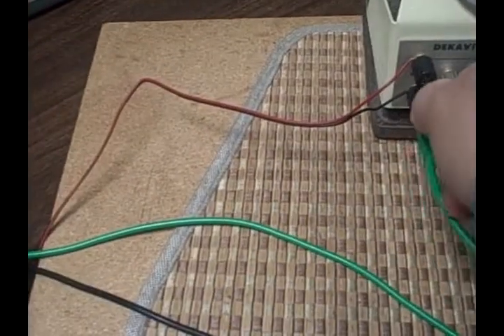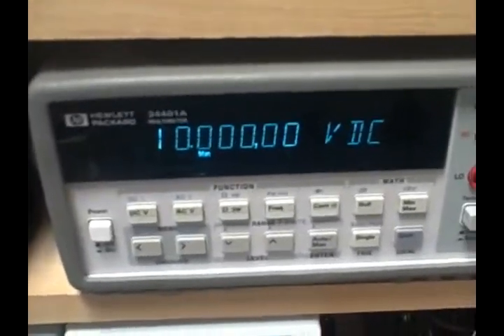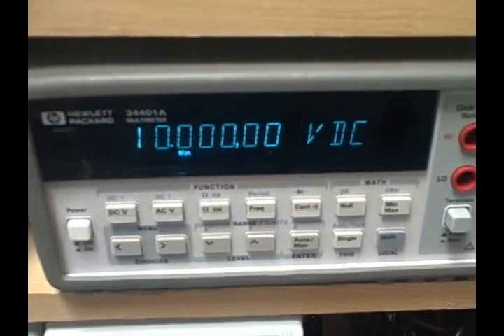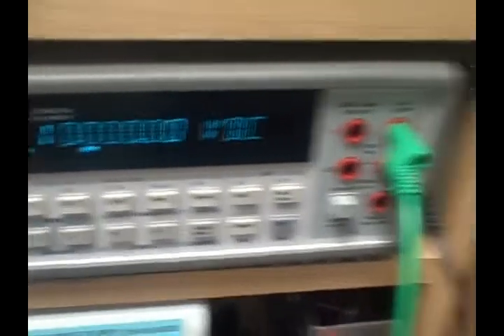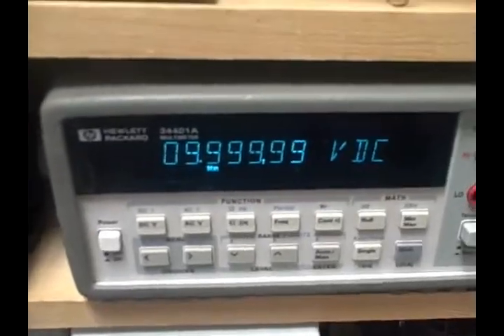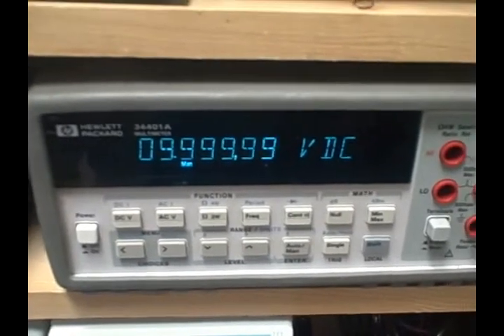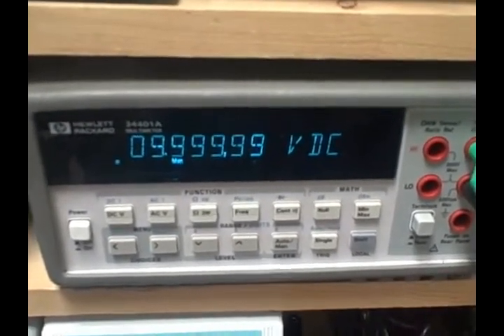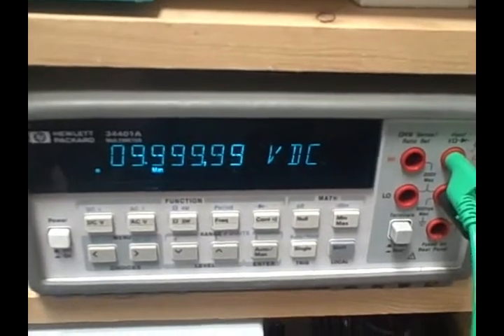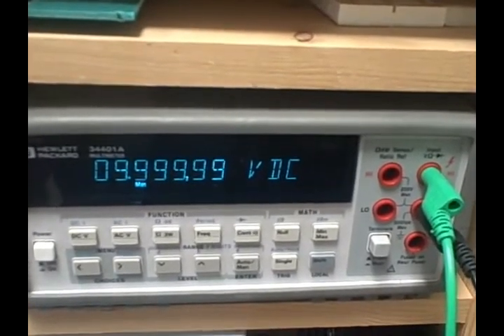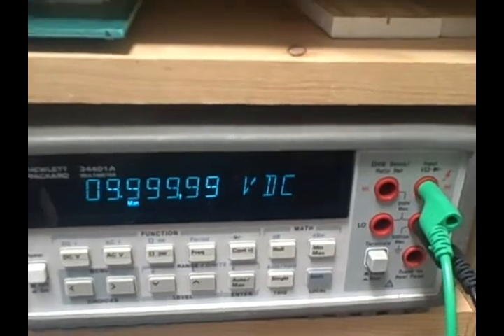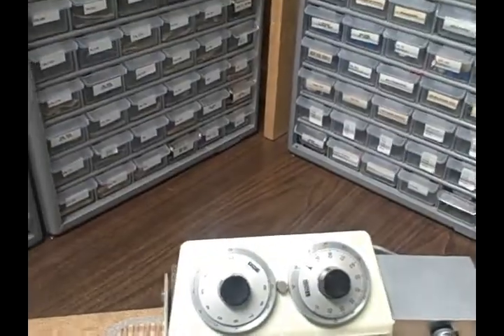And if I take a look at the input to the divider I see that I'm getting fed 10, with five decimal places of zeros in volts. And on the output I am getting all nines. So I'm within 10 microvolts of achieving a perfect 10 which would be the input voltage at this point. I'm up all the way in my divider.